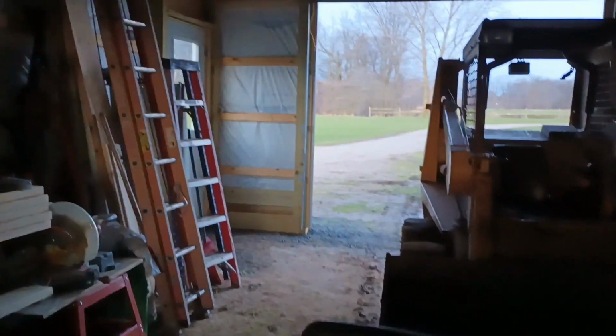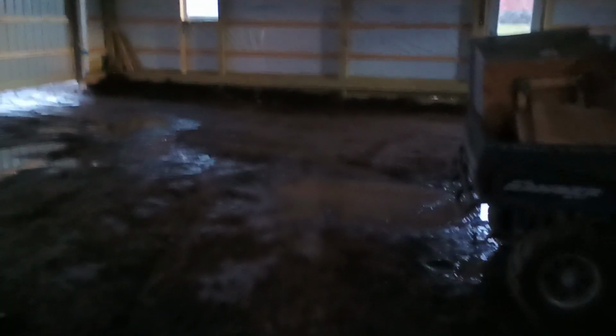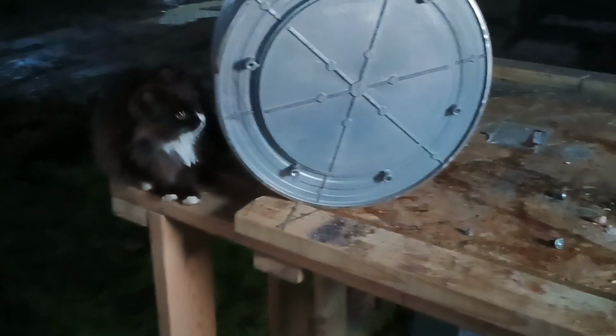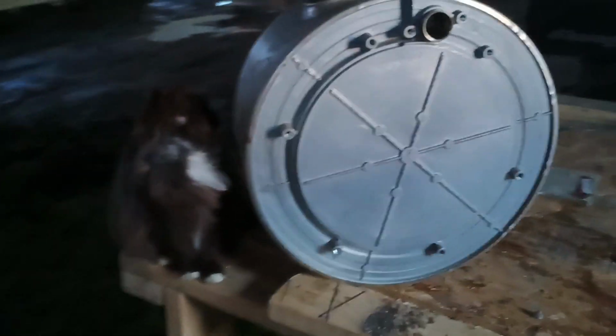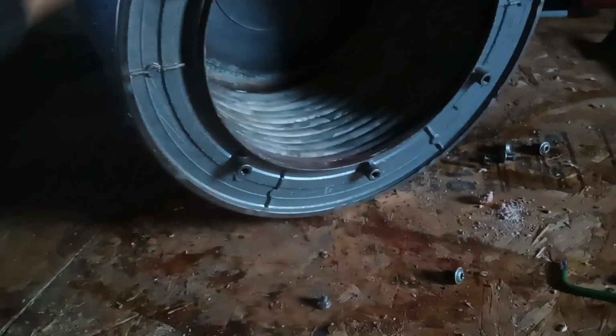So anyway, if you were to try to do in-floor heat in a space like this, this is about 1,800 square feet. If you don't do your load calculations, allowing for your reduction in capacity with antifreeze, you are going to be upset that your boiler is undersized and does not heat your little hobby shop. So keep that in mind and consult your HVAC professionals when you are doing design build stuff. It saves you a bunch of headache in the back end by working with guys that know what they're doing on the front end.